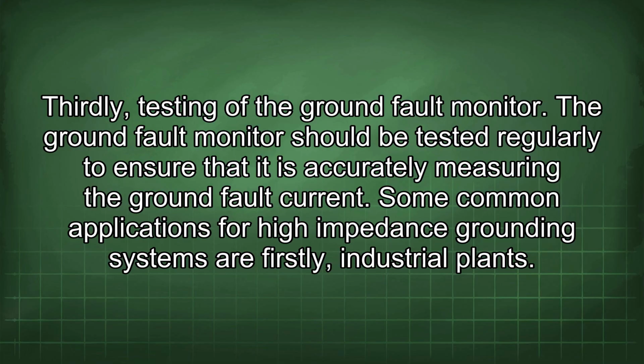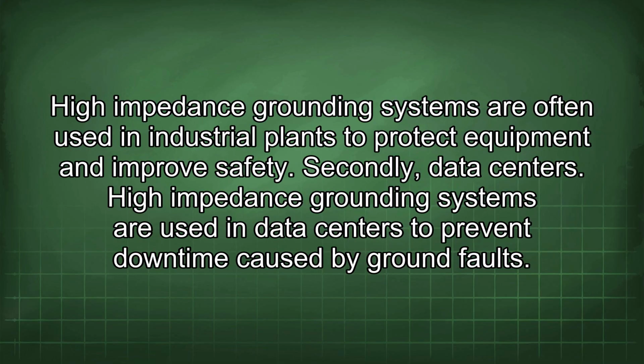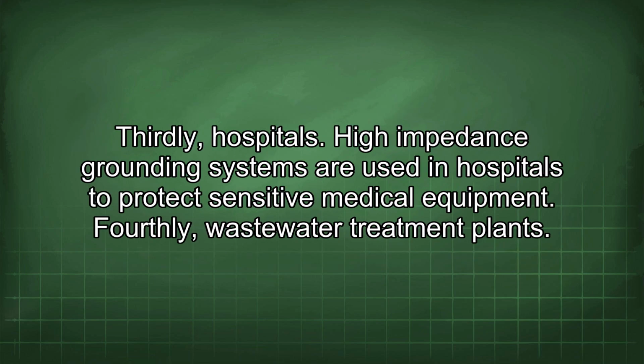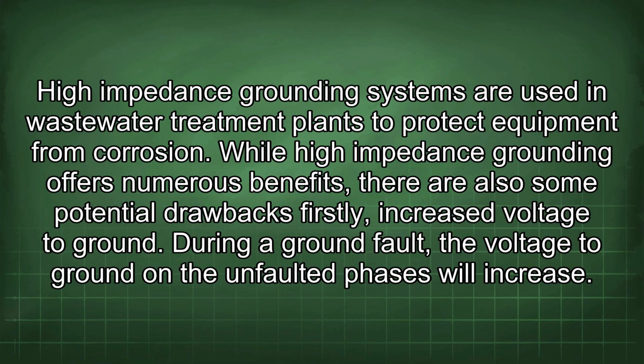Some common applications for high-impedance grounding systems are, firstly, industrial plants. High-impedance grounding systems are often used in industrial plants to protect equipment and improve safety. Secondly, data centers. High-impedance grounding systems are used in data centers to prevent downtime caused by ground faults. Thirdly, hospitals. High-impedance grounding systems are used at hospitals to protect sensitive medical equipment. Fourthly, wastewater treatment plants. High-impedance grounding systems are used in wastewater treatment plants to protect equipment from corrosion.